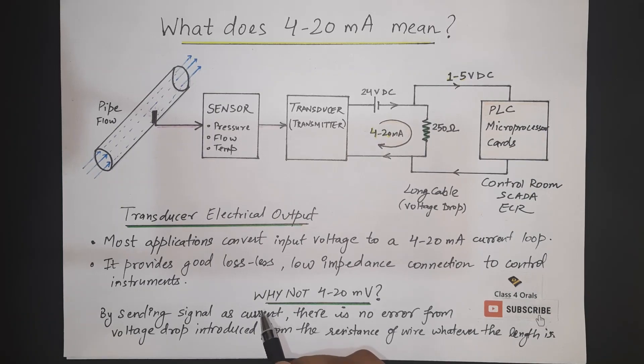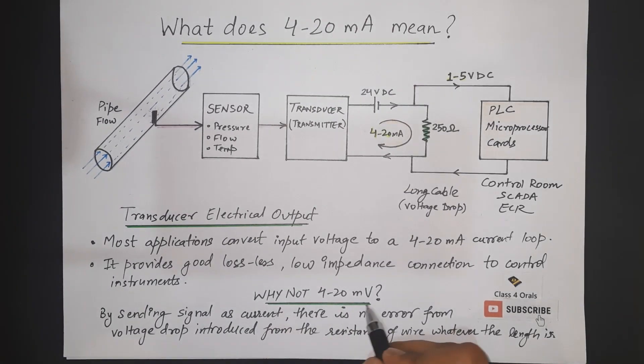Now the question arises why we are focusing only on the 4 to 20 mA and why not we are taking the 4 to 20 mV because by sending the signal as current there is no error from the voltage drop.